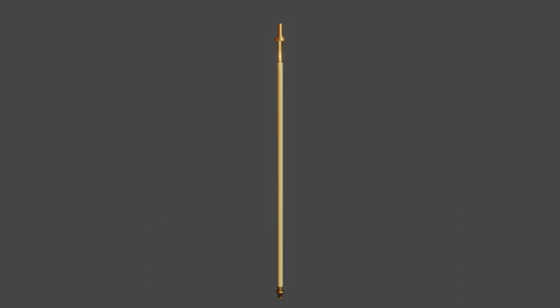This is the kraft paper wound on the conductor. The length and thickness of the kraft paper dielectric are calculated for proper distribution of voltage in a capacitor graded bushing. On that kraft paper dielectric, we wound aluminum foil. This foil acts as the metallic plate of the capacitor formed by the central conductor and the dielectric medium, that is, kraft paper insulation, and this aluminum foil.